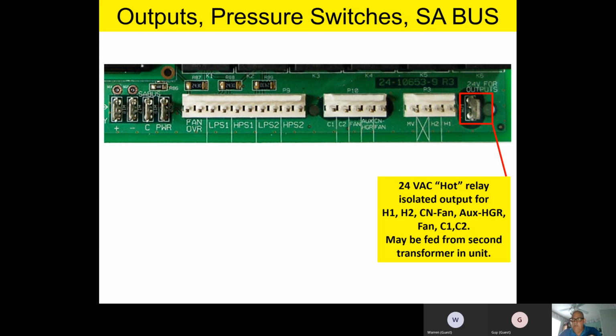You also may find that on your unit, if you have a little single-stage unit, you may not have anything hooked up to that 24-volt output. So just be aware that it's a 24-volt hot relay isolated output, and it may be operating things on a very large piece of equipment with a separate transformer, or it may not, based on the tonnage of the unit. It's just a 24-volt output, isolated relay output.